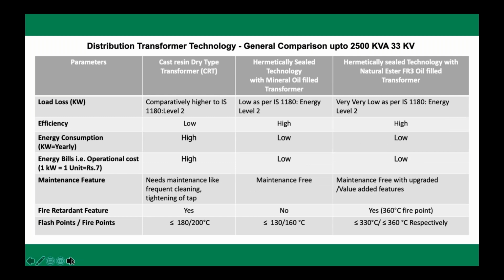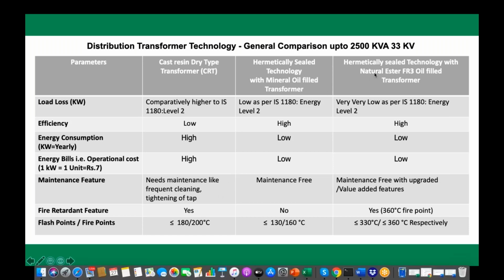Earlier, before implementation of IS 1180, there was a chance that the load losses of a liquid filled transformer could be more than the dry type transformer. But because of the efficiency requirements, today the transformers are really very low load loss transformers. That limits their current density, which was earlier a limitation for dry type transformers. That's the reason today oil filled transformer load losses are much lower than dry type transformers. And today people have started using aluminum in dry type transformers, which is a big nuisance, I would say. Although it suits that technology, it's a big nuisance, and I'll update you why when I come to the next slide.